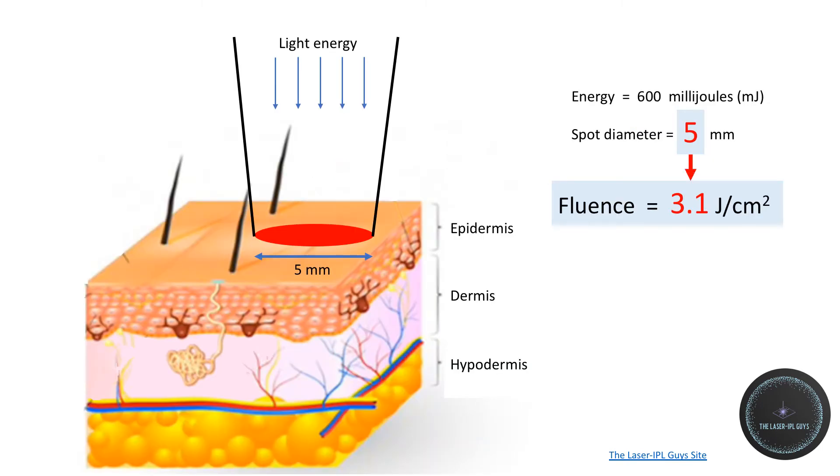If you set your laser for 600 millijoule output into a 5 millimeter spot diameter at the skin surface, then the fluence is simply the energy divided by the spot size area. In this case it would be 3.1 joules per square centimeter at the skin surface.